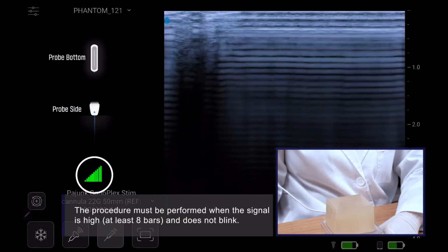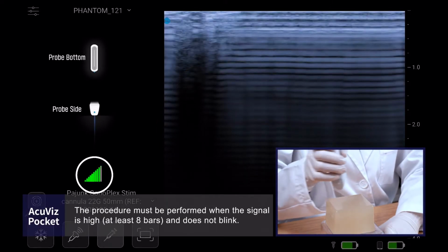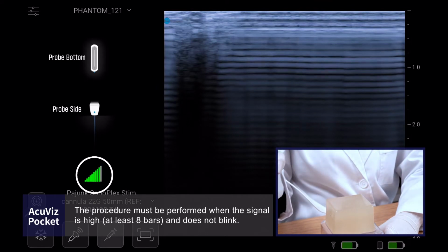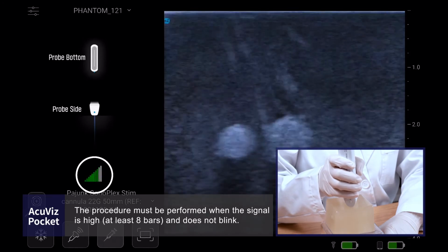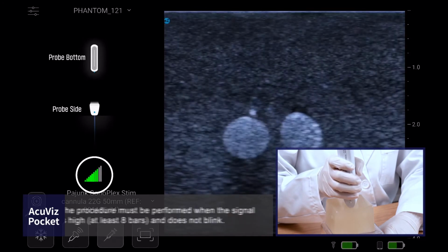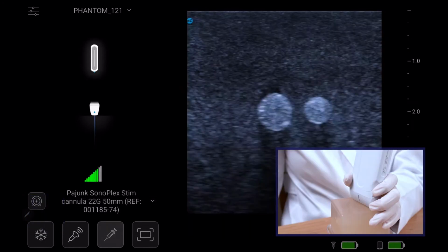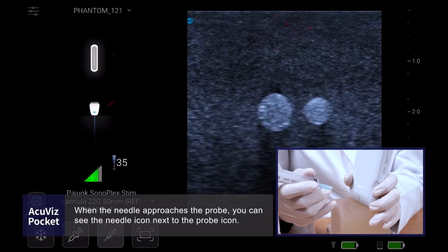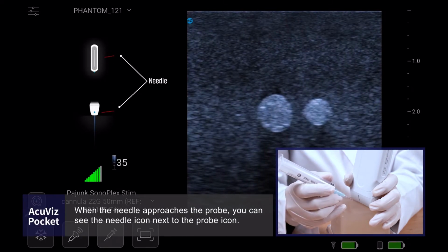The procedure must be performed when the signal is high, at least 8 bars, and does not blink. The signal blinks when the probe moves and stops blinking when the probe comes into contact with the phantom. When the needle approaches the probe, you can see the needle icon next to the probe icon.